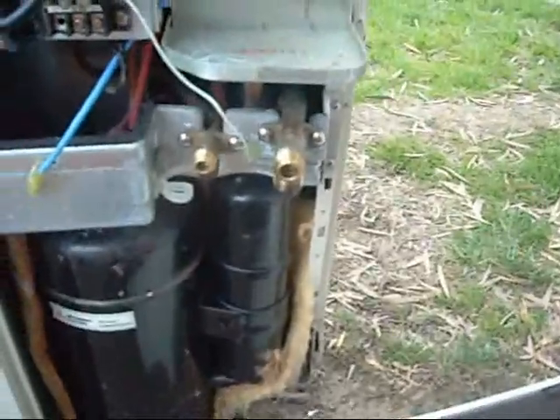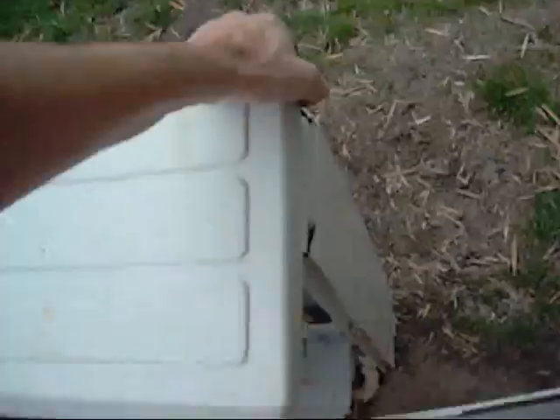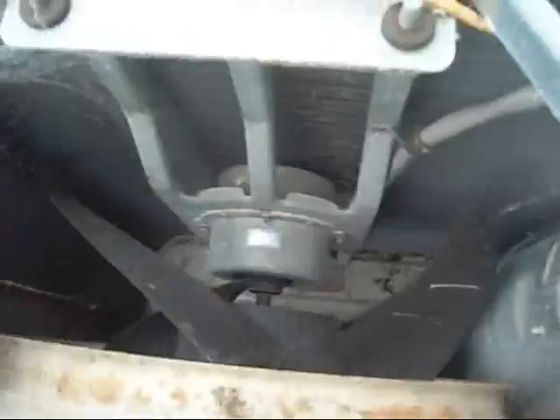The compressor's definitely burnt — I've already owned it, I know it's bad. It's been recovered, it had burnt refrigerant in it. Time to pull the covers off. That screw was seized — not anymore. Still a couple more screws to go. There's nothing special in these. Giant spiderweb as usual — I think most of them are dead, I hit this one with Mortein a while ago.